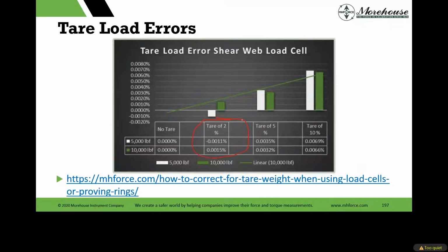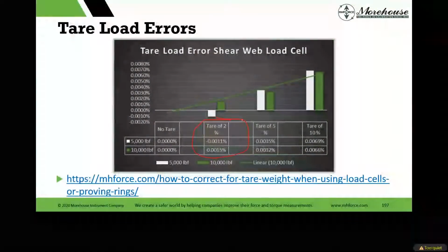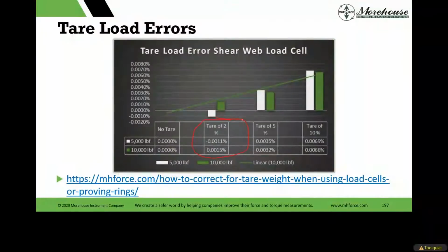I'm very comfortable telling people with a shear web load cell that if you don't exceed 2% of the capacity, meaning if a 100K Cal machine weighs the Tare's 500 pounds, 50,000 pound, 1%, 25,000 pound, 2%, no problem. 10,000 pound load cell with a 500-pound tare, you're at 5%. You're going to have some additional error. And as soon as you start taring out more, different load cells will act differently for this. So, general rule of thumb is 1 to 2% of the load cell capacity for your tare weight, and you're fine.